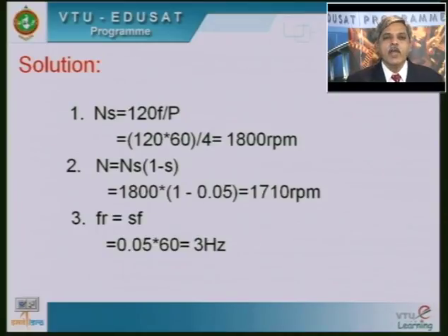We need an equipment or a device to measure the speed under full load condition. Otherwise, it is not possible to make out that the motor is running at a reduced speed of 1710 RPM under full load condition. Since the difference in the speed is quite small compared to the rated speed or the synchronous speed, I say the induction motor is almost a constant speed motor.